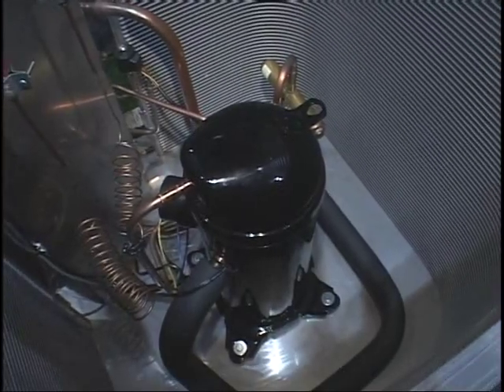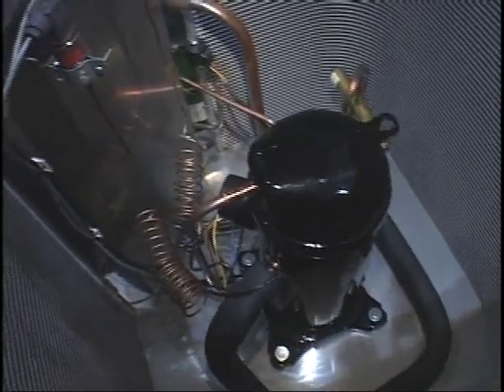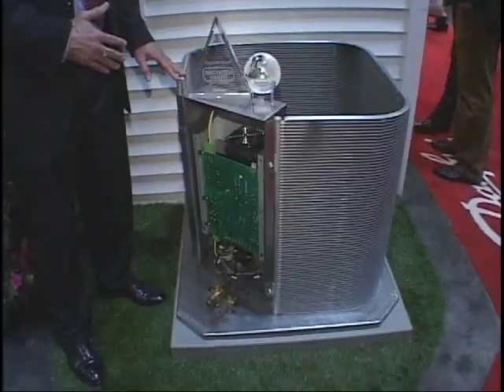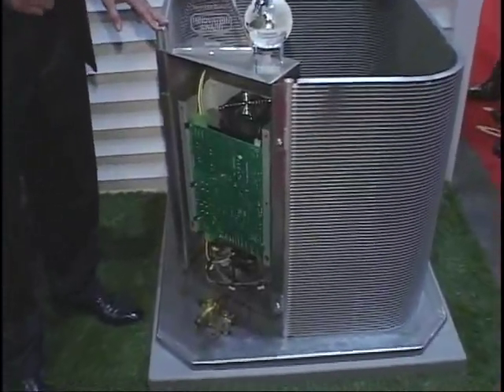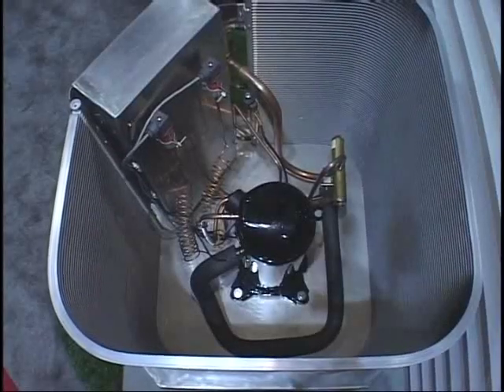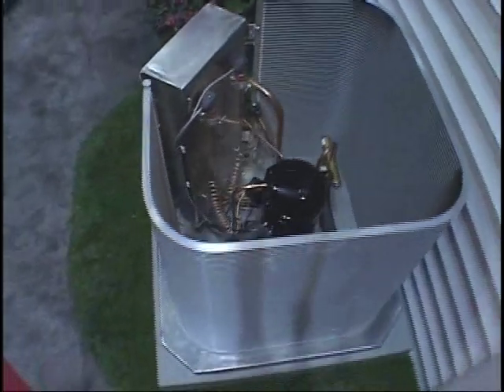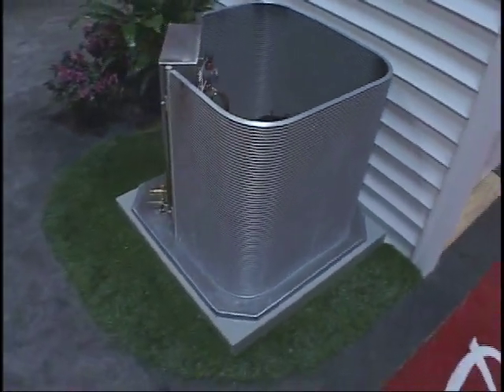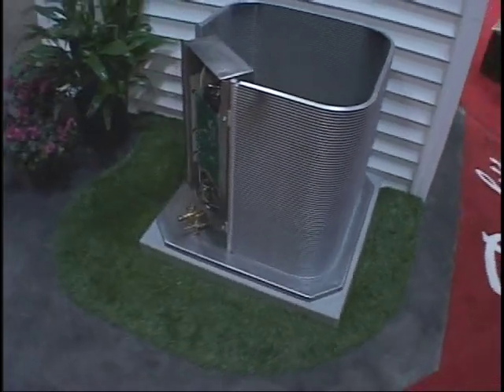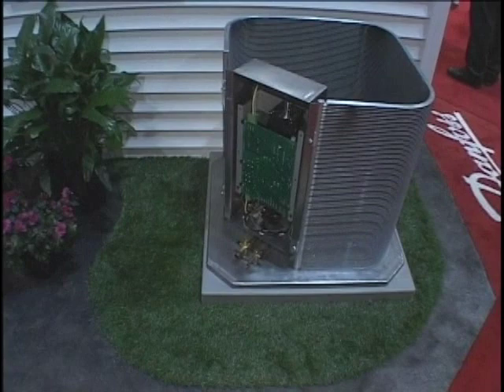If you look inside, the compressor looks like a normal compressor, but it's not. It's got a complete controller here for variable frequency drive, which drives the speed high and low to meet the actual load demand. It also has communication capabilities, so this can actually be tied into smart metering or smart grid, so that if you get into a peak demand situation, the power company can actually start to lower back the speed of the compressor to manage peak demand rather than shutting the system off. So you're allowing higher efficiency while at the same time continuing to provide comfort.